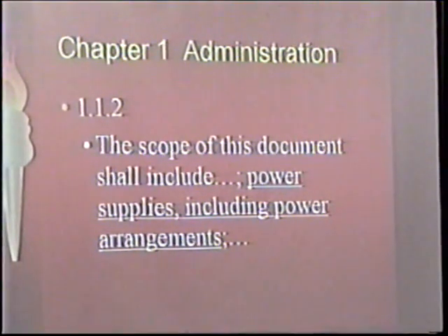Well, today, now in the new 20, it says that that's not acceptable. It's finally in there that a standby power supply is not an acceptable power source for a fire pump. It is if it's an alternate to a continuous source, but not as a sole source.